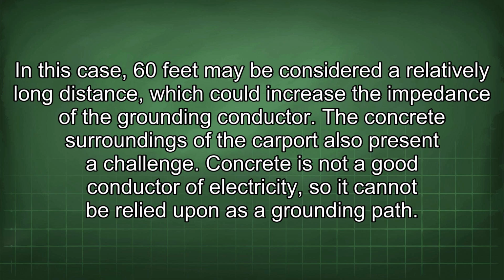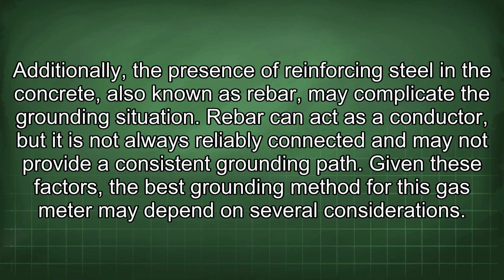Concrete is not a good conductor of electricity, so it cannot be relied upon as a grounding path. Additionally, the presence of reinforcing steel in the concrete, also known as rebar, may complicate the grounding situation. Rebar can act as a conductor, but it is not always reliably connected and may not provide a consistent grounding path. Given these factors, the best grounding method for this gas meter may depend on several considerations.